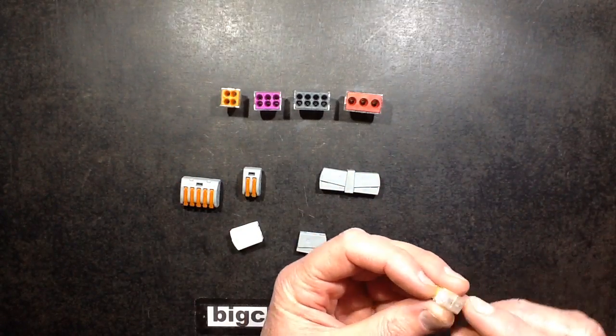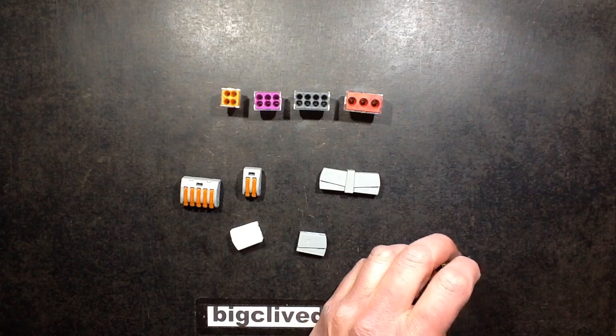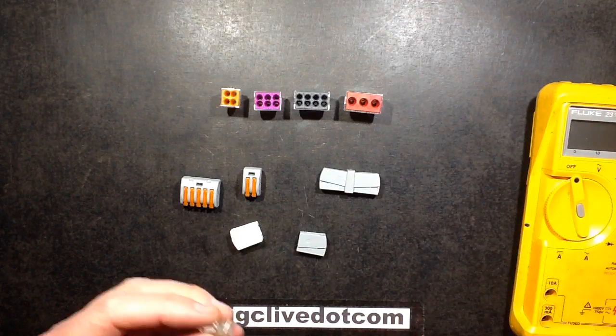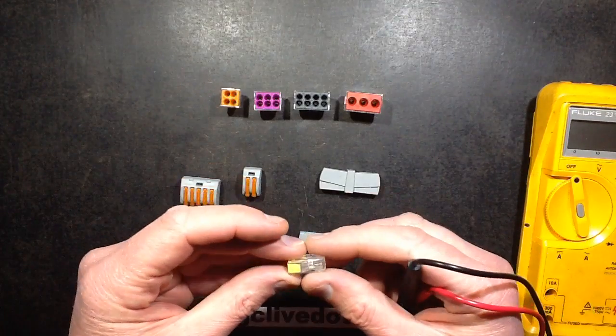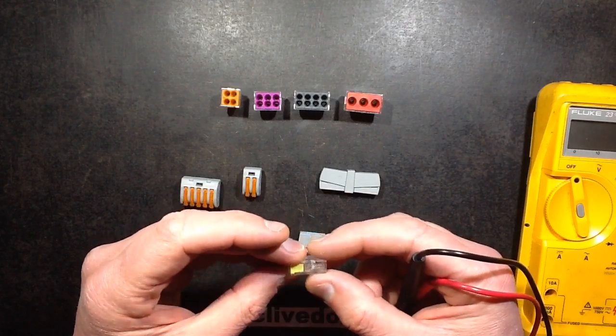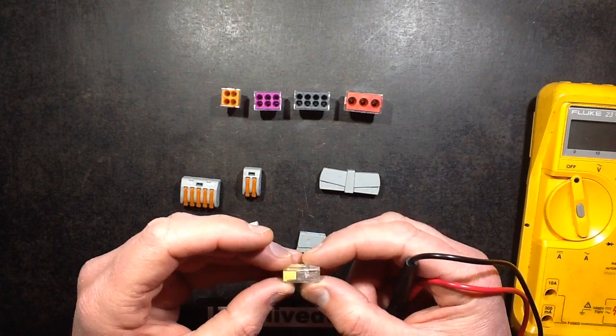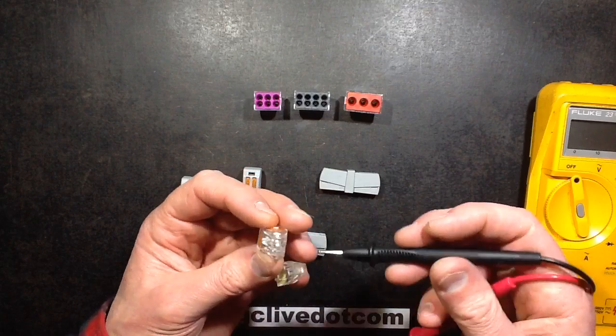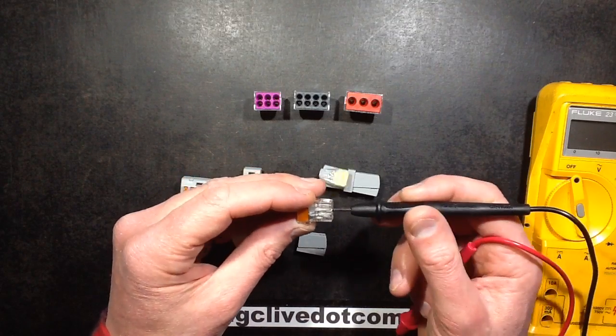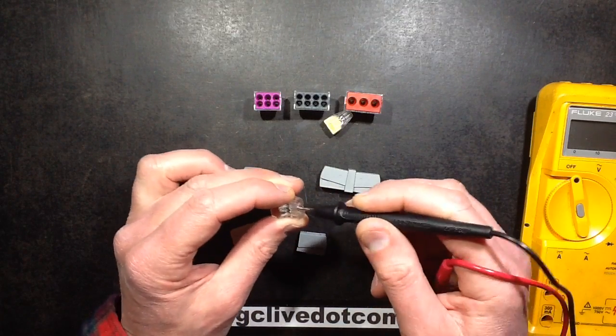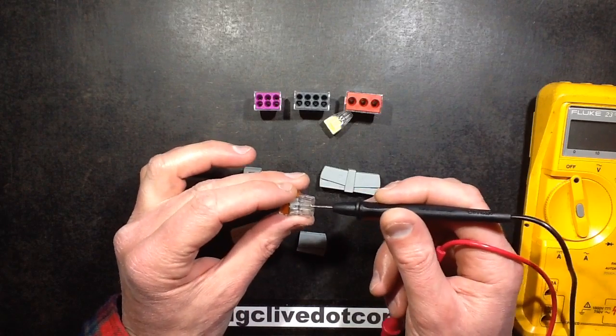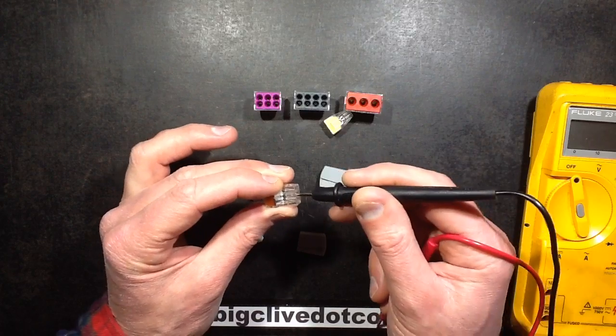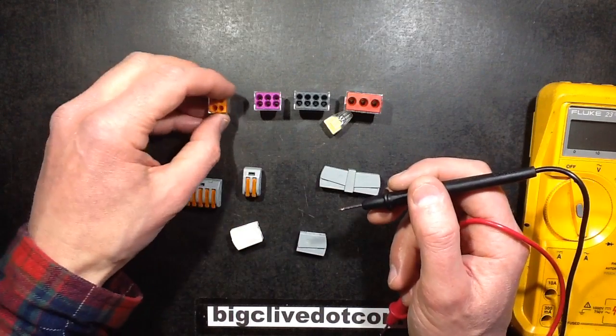They've got some interesting features. If you're wanting to do electrical tests then any of these units has a test facility. You can actually just take a terminal and at the back of it you can poke terminals into it and it's shielded enough that you're not going to accidentally poke wires in, but it lets you make connection with the back of the little springy bus bar inside which is very good.